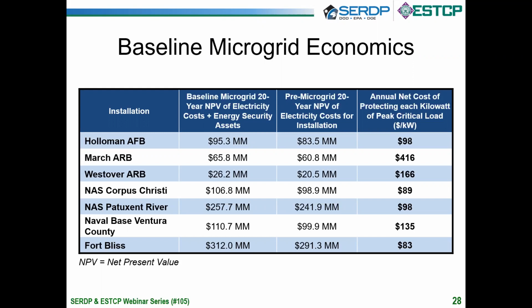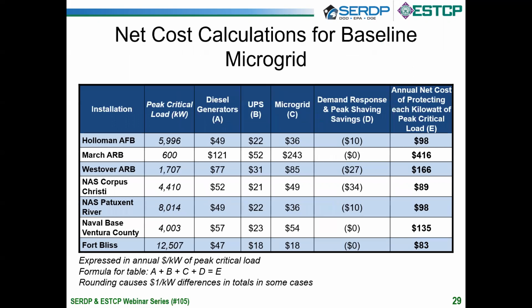And to standardize that by what it is serving, mission-critical loads. We want to pinpoint where microgrids effectively cost you more or less on a life cycle basis among installations, compared to the status quo, and compared to microgrids with storage. To that end, you'll see large variations between baseline microgrid costs on this chart at Fort Bliss or Corpus Christi and those at March Air Reserve Base, if you look on the far right. The next slide explains why. Please go to slide 29.